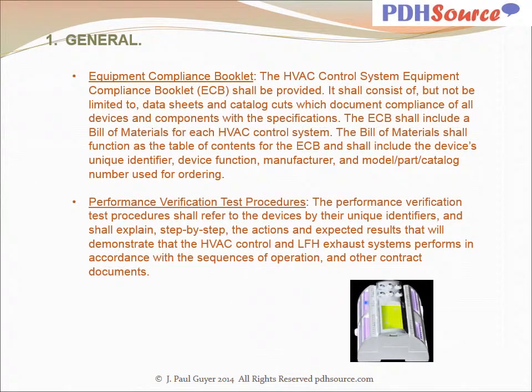The HVAC control system equipment compliance booklet shall be provided. It shall consist of, but not be limited to, data sheets and catalog cuts which document compliance of all devices and components with the specifications. The equipment compliance booklet, ECB, shall include a bill of materials for each HVAC control system. The bill of materials shall function as a table of contents for the ECB and shall include the device's unique identifier, device function, manufacturer, and model part catalog number used for ordering.